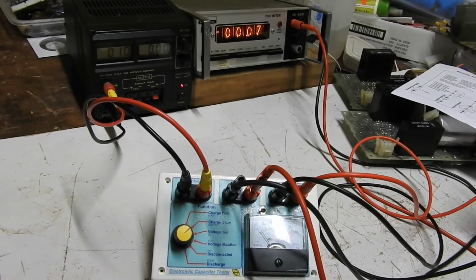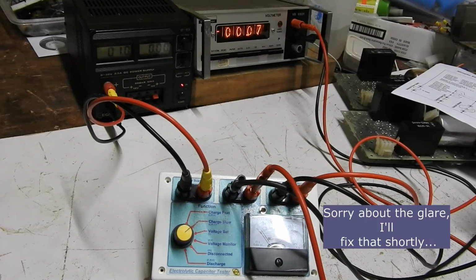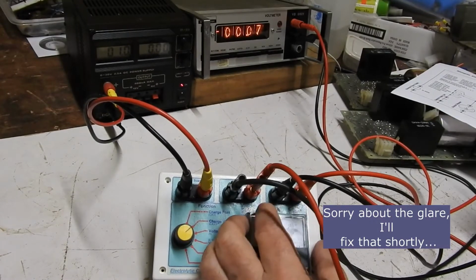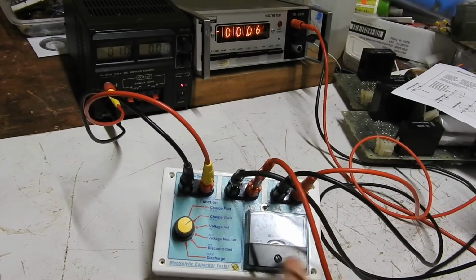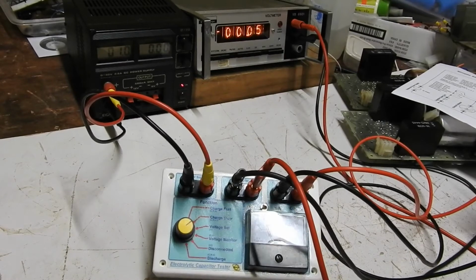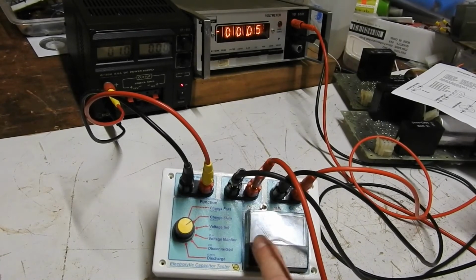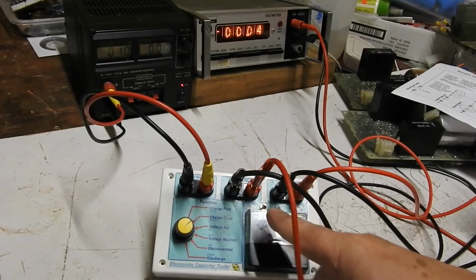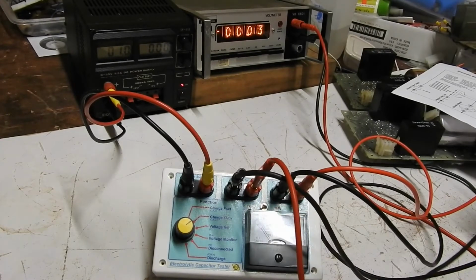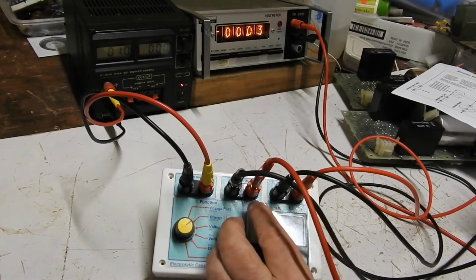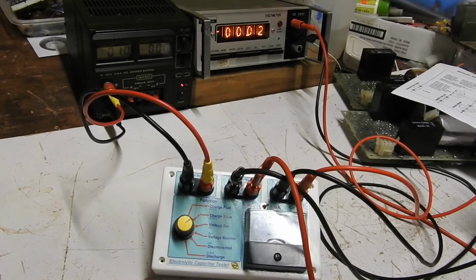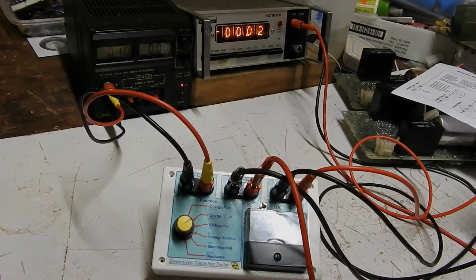Very low current because we're only pushing a volt, so we can almost switch to microamps. No, it's beyond that, got to wait for it. We want to get almost to 0, because remember that's a 1,000 times change in current. So almost nothing here is still off the scale in microamps.